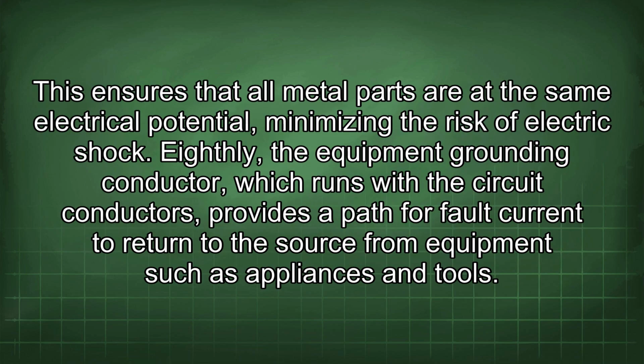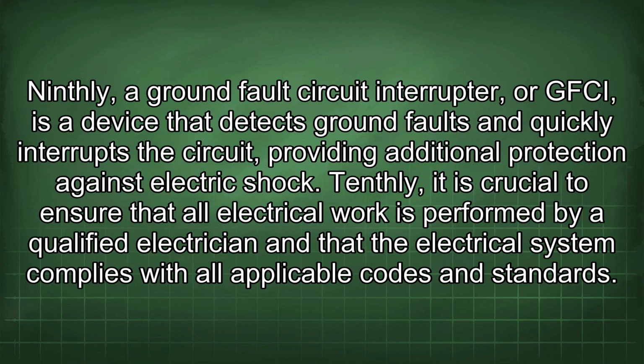Seventhly, bonding refers to the connection of all non-current carrying metal parts of the electrical system to the grounding system. This ensures that all metal parts are at the same electrical potential, minimizing the risk of electric shock. Eighthly, the equipment grounding conductor, which runs with the circuit conductors, provides a path for fault current to return to the source from equipment such as appliances and tools. Ninthly, a ground fault circuit interrupter, or GFCI, is a device that detects ground faults and quickly interrupts the circuit, providing additional protection against electric shock.